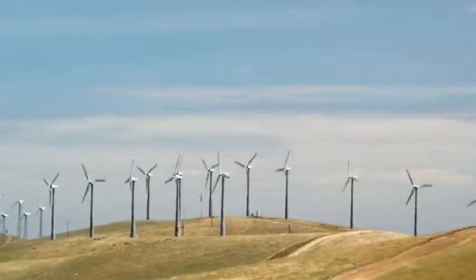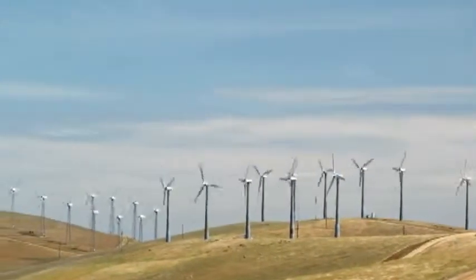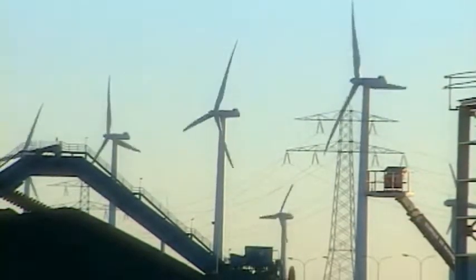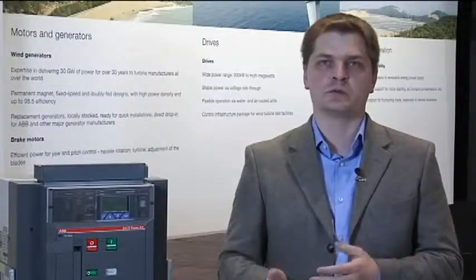In this video we have seen how wind turbine manufacturers resolved the problem of new restricted grid regulation by using a permanent magnet generator that can always be connected with the grid even if the grid has any kind of issue. We have also seen how to fix the problem of protecting this kind of wind turbine generator, which requires variable frequency protection. The perfect solution is a circuit breaker that can work in a variable frequency environment.